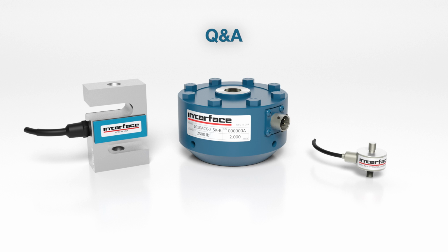150% overload. Does that mean no damage to the strain gauges at 150%? At what overload is there physical damage to the cell? We would expect the load cell to not suffer any permanent deformation up to 150% of capacity. Past that point, you could suffer some permanent damage to the gauged areas. This would be manifested either by a shift in zero balance or, again, as previously referenced, the RCal shunt value may be different.